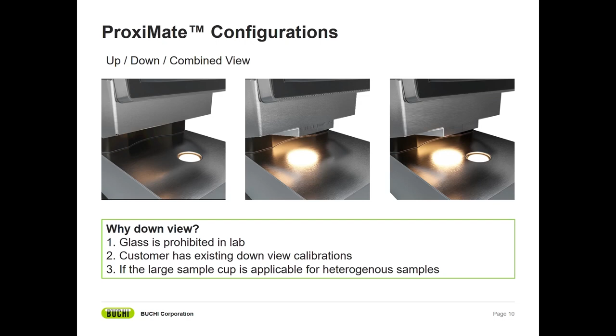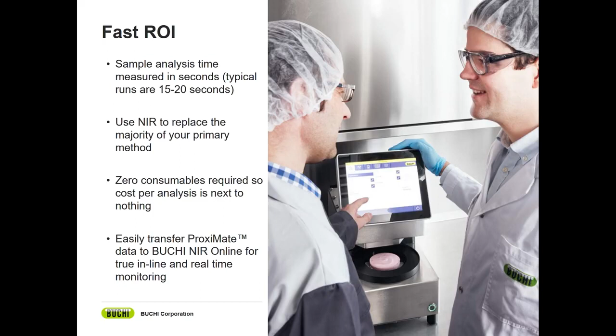So one more point that I like to highlight is the really nice potential for a fast return on investment if you put the time in up front to get your calibration situated the way you want it. Not only is NIR significantly faster than primary techniques like Kjeldahl or Dumas, but it also requires zero consumable consumption, making the cost per analysis next to nothing. Even better is that the work and effort put into your benchtop calibrations can then be later used for NIR online applications, since the two really go hand in hand.